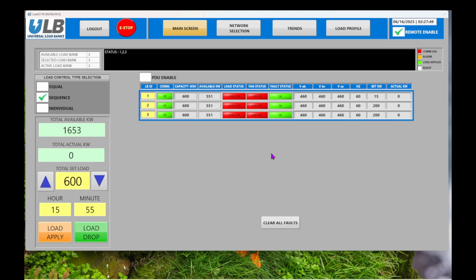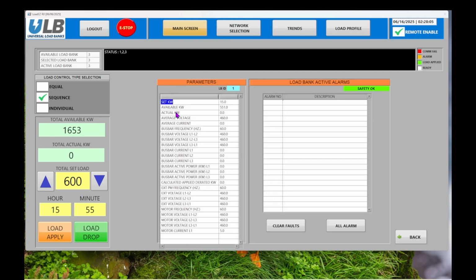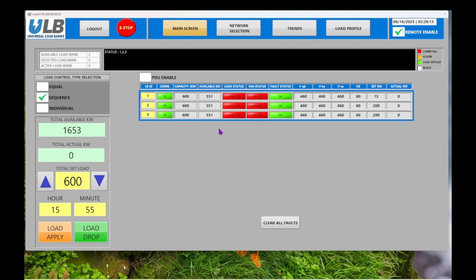On this screen, you'll see the total number of load banks detected on the network, the number of selected load banks, and the number of active load banks currently in operation. You can select up to 200 load banks for control. To monitor a specific load bank, simply click on its ID. This brings up individual parameters, real-time data, and alarm information for that unit. Ideal for monitoring and troubleshooting. Press the back button to return to the main screen.